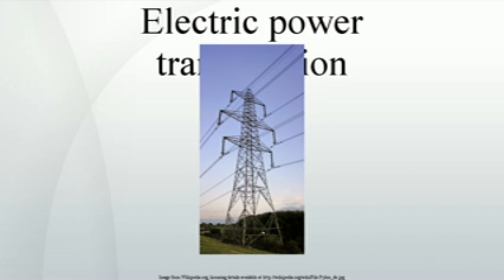High-voltage direct current, HVDC, technology is used for greater efficiency at very long distances, typically hundreds of miles, kilometers, or in submarine power cables, typically longer than 30 miles, 50 kilometers. HVDC links are also used to stabilize and control problems in large power distribution networks where sudden new loads or blackouts in one part of a network can otherwise result in synchronization problems and cascading failures.